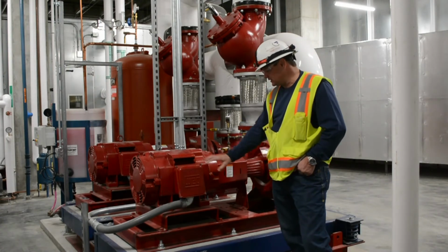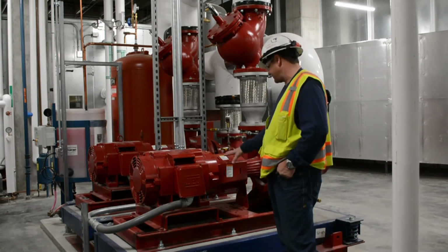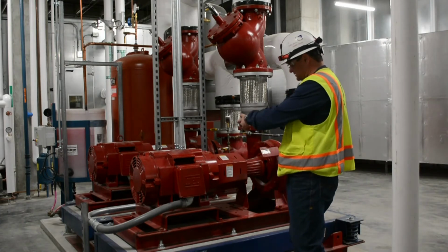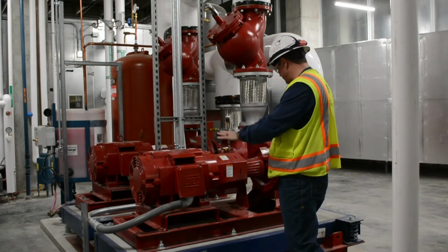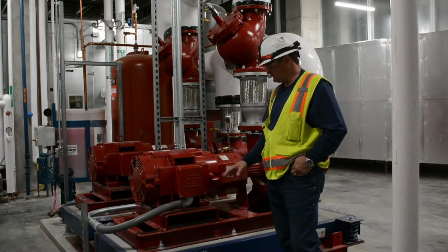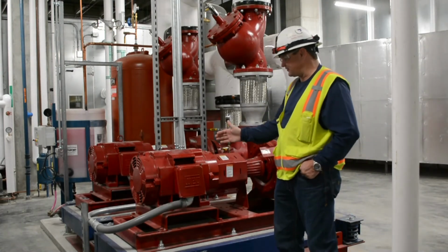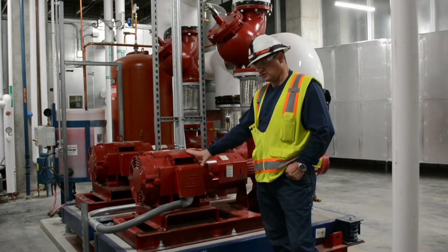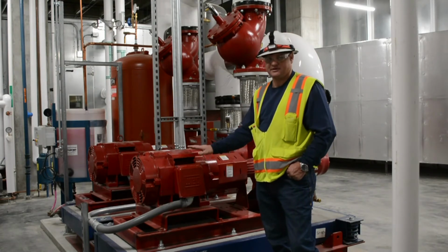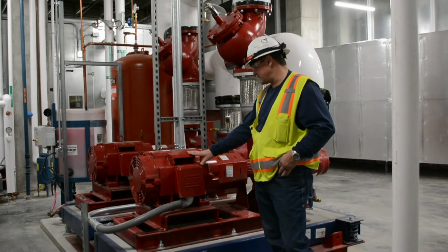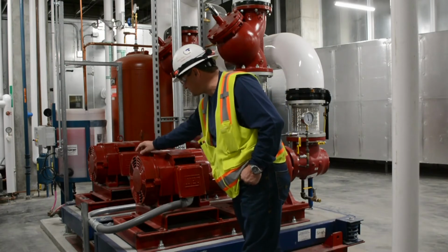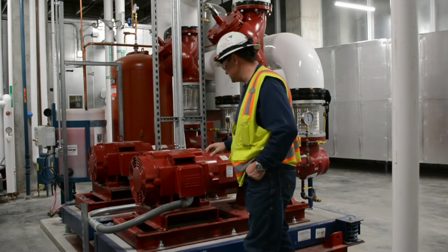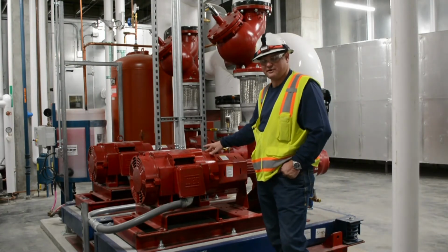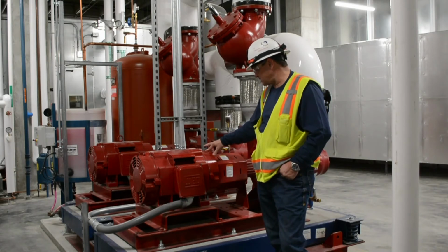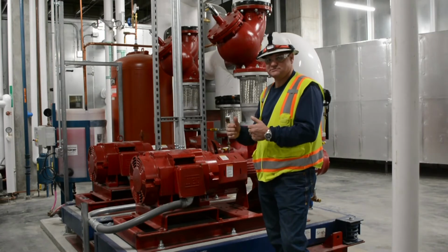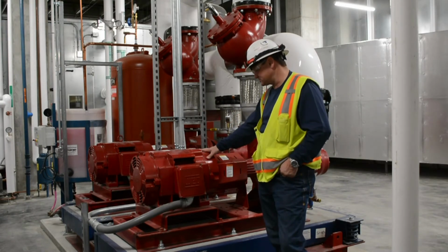If you ever have to remove the motor, you will have to realign the motor with the coupling. The best thing to do is to try to actually just get the coupling sheaves separated without moving the motor or the pump itself, and then you don't have to align it again. But if you do move the motor, you will have to align it. They need to be aligned within 5/1000 of an inch, which has already been done for you. However, if you do need to do that, again, I'd recommend you have somebody trained that knows how to do pump alignment correctly. There are zerks on these motors for grease. About every 8,000 run hours is when you'll want to add grease. You only need about 1.5 ounces of approved Polyrex grease. So that's about 1 to 1.5 pumps of a grease gun into that bearing in order to properly lubricate it.